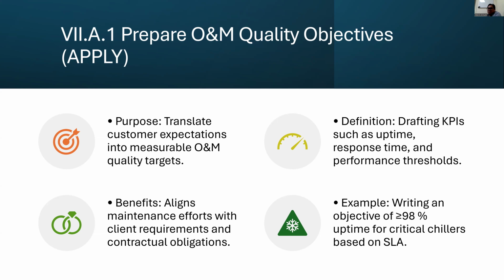Example: writing an objective of equal to or higher than 98% uptime for a critical chiller based on the SLA. So 98% uptime is good—in 360 days, your downtime should only be about six days. But take note, this applies provided there is a standby, meaning this is for unscheduled downtime. If it is scheduled downtime, it will not affect the KPI, of course.